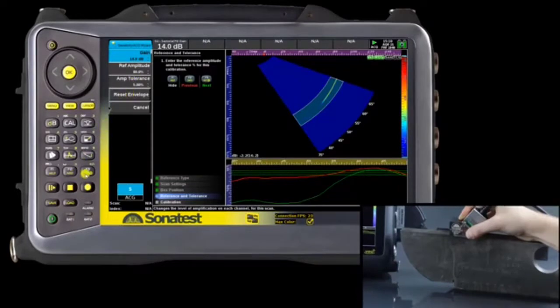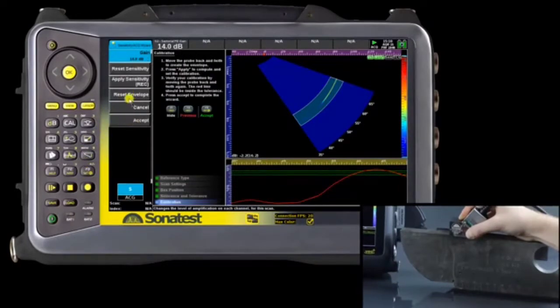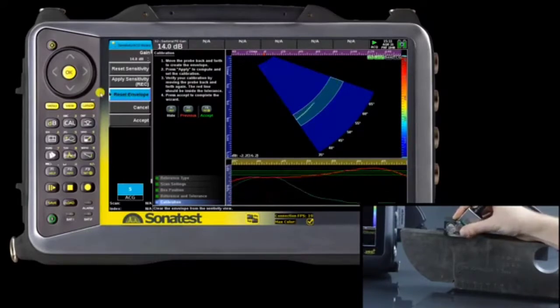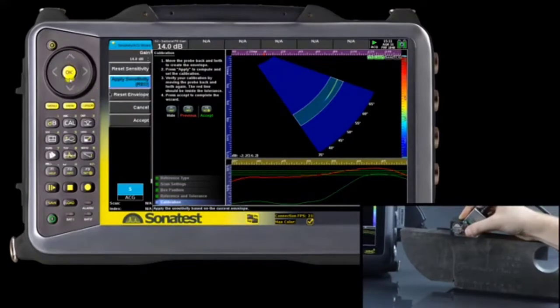Before recording the signal, or if a mistake occurs, we can reset the envelope before applying the sensitivity. Once the envelope has been recorded, we can apply the sensitivity gain correction to the signal. At this stage, we recommend you do a validation of the signal correction. We can now see that the signal for the 60-degree angle is slightly off tolerance. If this occurs, we need to sweep again the reference and reapply the sensitivity correction until the signal is within the expected tolerance.